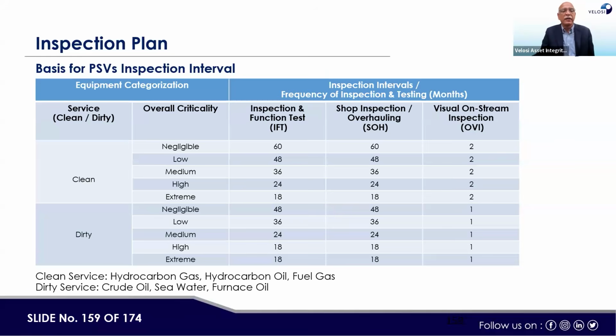Here you can see the equipment categories, like service, clean or dirty, and overall criticality point of view, inspection, functional test, these are the months. Shop inspection overhauling, these are the frequencies, and visual on-stream inspection, these are the numbers. This is the criteria for the determination of the intervals, like 60 months, 48 months, 36 months for the clean service. Then shop inspection overall, 60, 48, 36. Visual inspection on stream, 2 months, 2 months, 2 months.